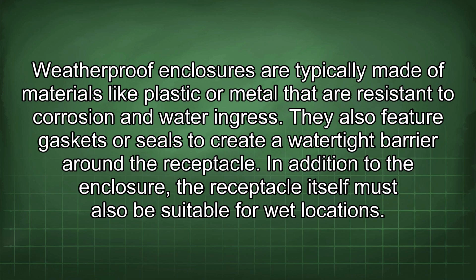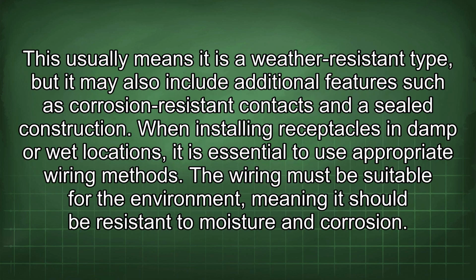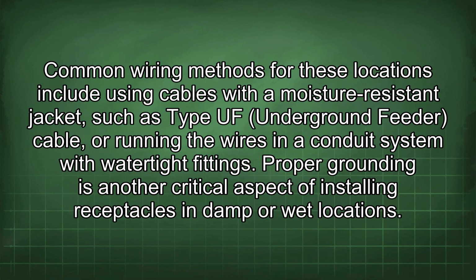In addition to the enclosure, the receptacle itself must also be suitable for wet locations. This usually means it is a weather-resistant type, but it may also include additional features such as corrosion-resistant contacts and a sealed construction. When installing receptacles in damp or wet locations, it is essential to use appropriate wiring methods. The wiring must be suitable for the environment, meaning it should be resistant to moisture and corrosion. Common wiring methods for these locations include using cables with a moisture-resistant jacket such as Type UF underground feeder cable, or running the wires in a conduit system with watertight fittings.